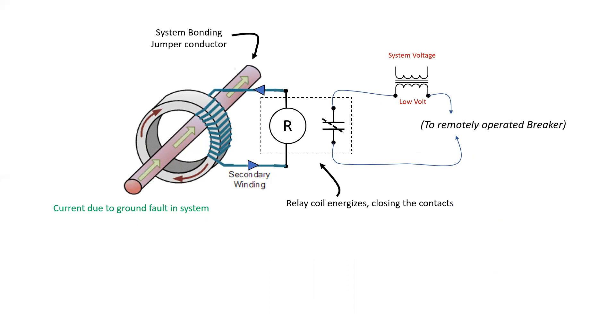Since current is flowing through the secondary of the CT, it will cause a voltage to be developed, which should then energize the coil on our relay. The relay coil energizes, closes the contacts, which then applies voltage to the remote trip mechanism in the breaker and opens the breaker, thereby de-energizing the system.